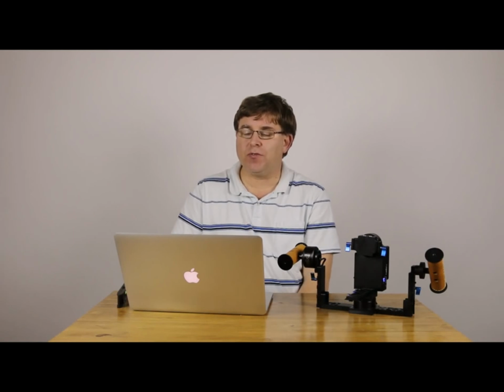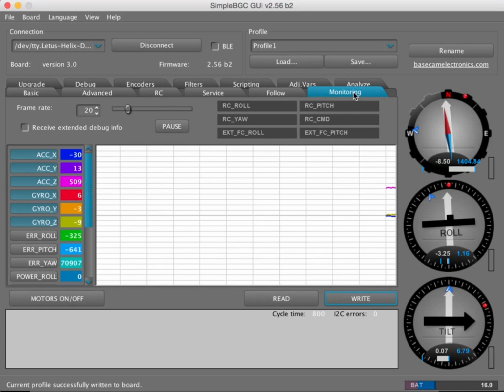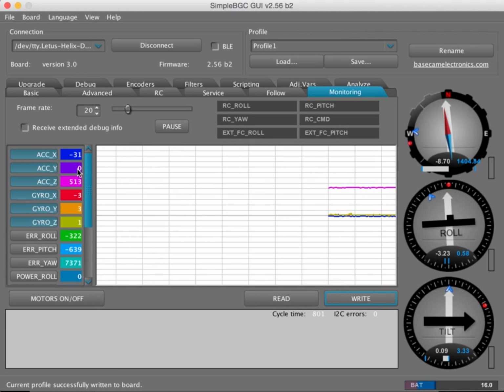in a separate video. The first thing we're going to do, before we even do calibration here, is talk a little bit about how you know if your calibration even needs to be redone. We'll come over here to the monitoring tab, and you can see some of this data here. We have 6 values here, 3 for accelerometers, 3 for gyros. The values here for the gyros, when the motors are completely off, like this, we're not touching it, should be between -3 and 3.